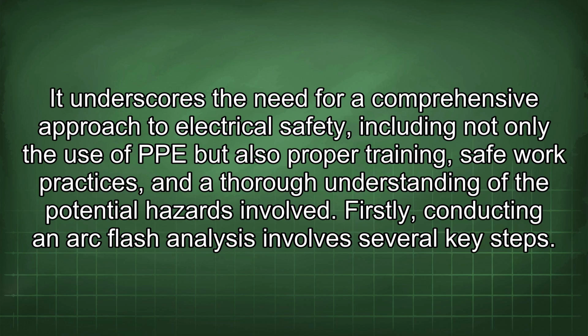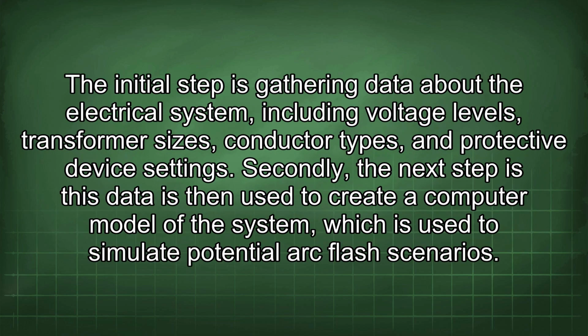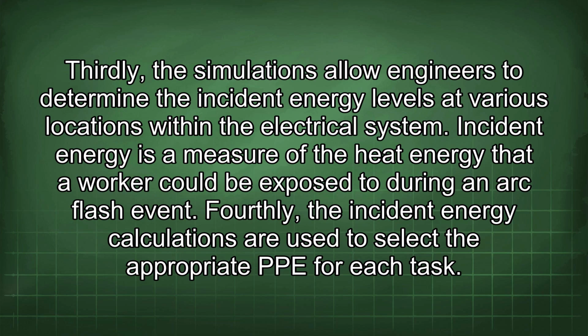Firstly, conducting an arc flash analysis involves several key steps. The initial step is gathering data about the electrical system, including voltage levels, transformer sizes, conductor types, and protective device settings. Secondly, this data is then used to create a computer model of the system, which is used to simulate potential arc flash scenarios. Thirdly, the simulations allow engineers to determine the incident energy levels at various locations within the electrical system. Incident energy is a measure of the heat energy that a worker could be exposed to during an arc flash event. Fourthly, the incident energy calculations are used to select the appropriate PPE for each task.